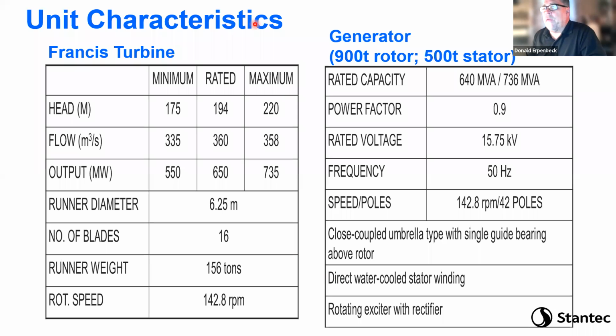Right, some information on the project. For the turbine, the maximum power out of that turbine is 735 megawatts. Rated is 650. At minimum water levels, it can still produce 550. The turbine runner itself, which is just the wheel of the turbine, is 156 tons. The generator on the other side weighs 900 tons on the rotating parts, and the stationary part of the generator is 500 tons. So a lot of the mass is here.